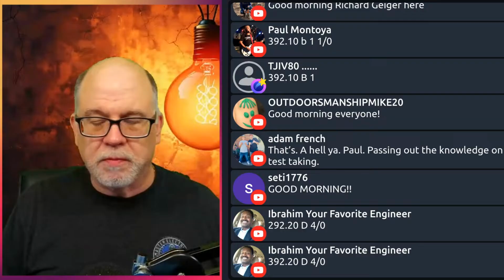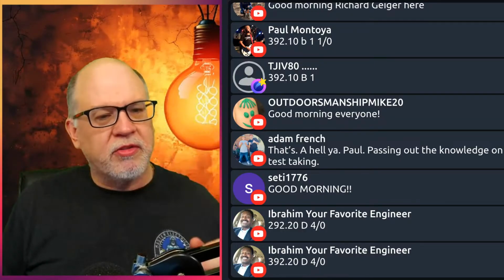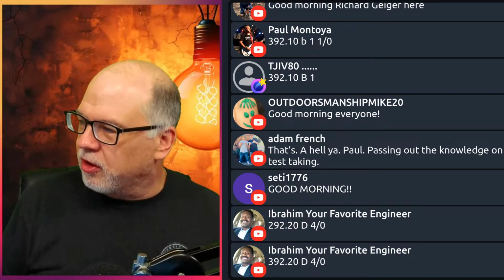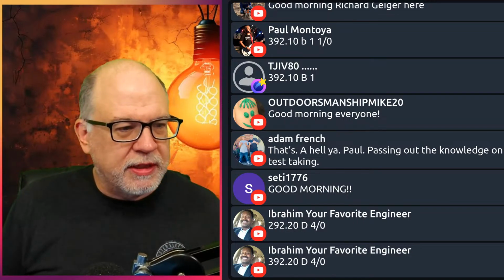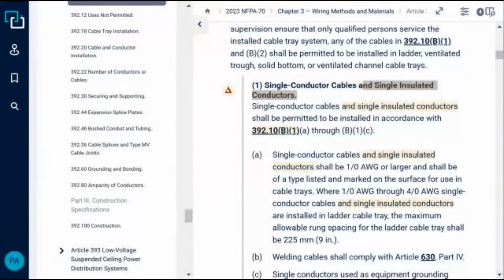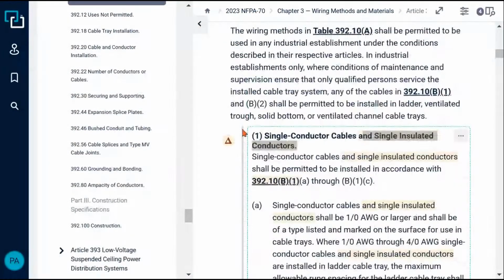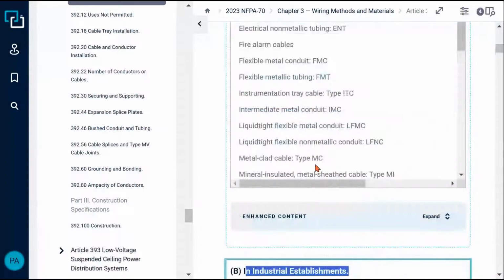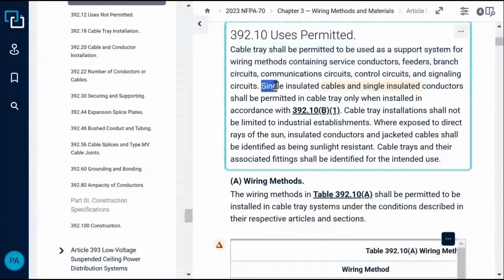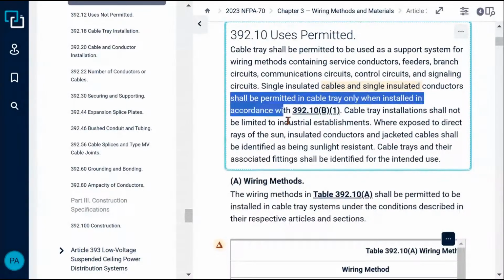At the end of the day, that was one of those things where I realized it. So if you go down here, under B, industrial establishments - because A tells you all about it - it says single insulated conductors and single conductor cables shall be permitted in cable trays only when installed in accordance with 392.10(B)(1). So that's the rule, folks, that tells you single insulated conductors like XHHW, THHN can't be in a cable tray.